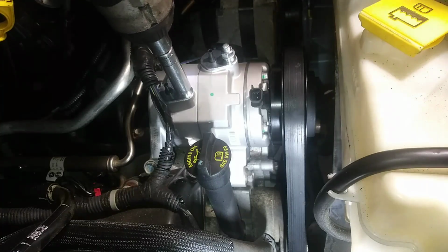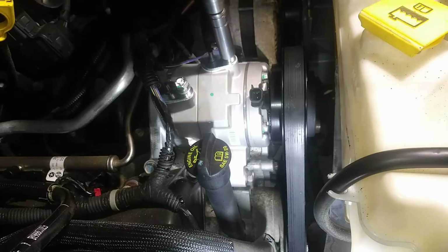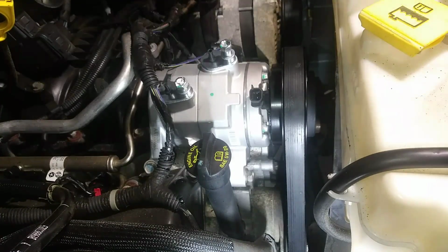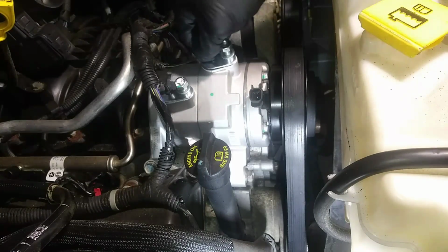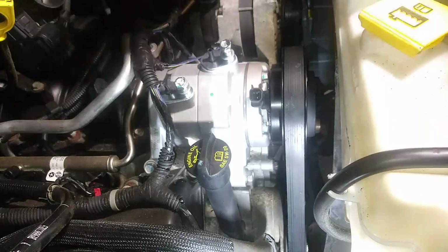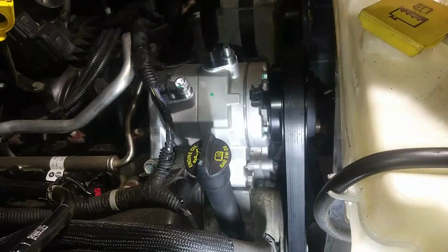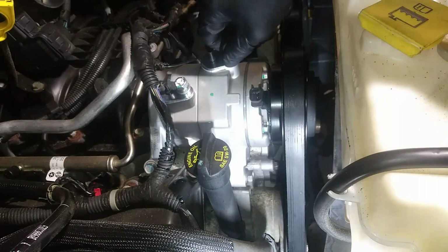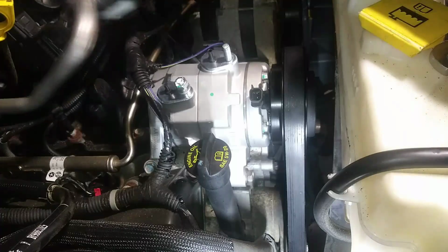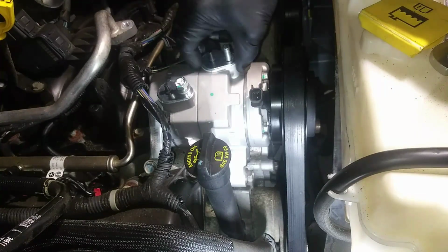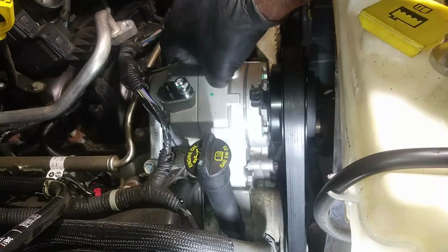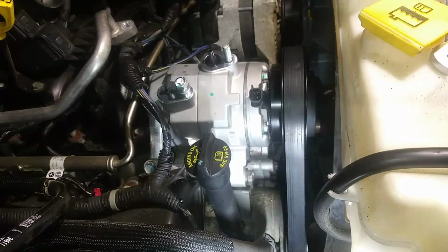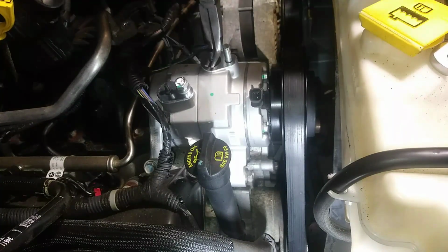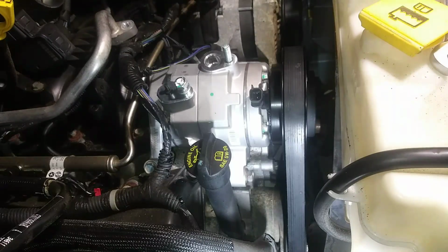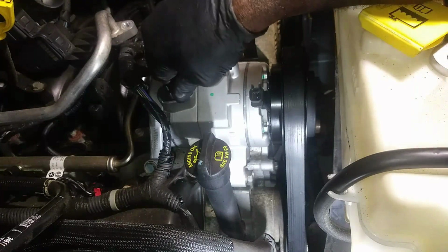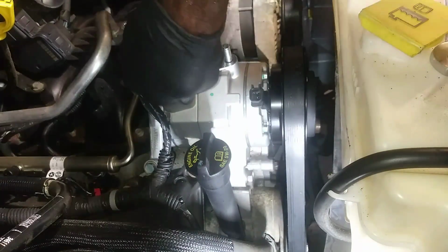Now there's going to be some pressure in here, so I'm going to be mindful of taking these rubber inserts out. Ideally you want to take it off on the suction side since it should suck, but I think the whole thing is filled with some type of pressure. Let's see what happens. Typically I'll spin the compressor the other way and it'll shoot out. So if I wasn't filming, I would do that.